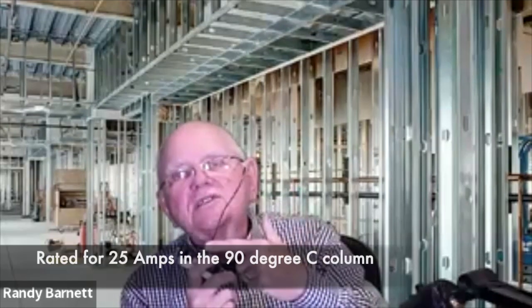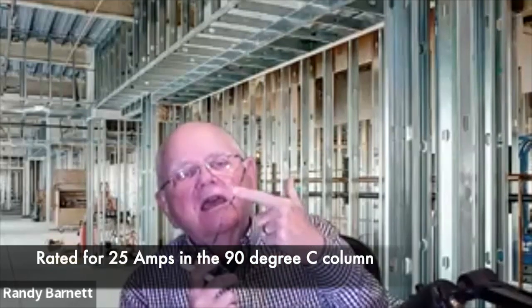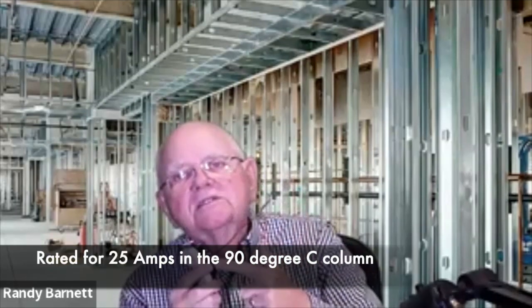Well, should it? No. I've got a wire that's rated for 25 amps, and it's limited because of the device, which is inside of a box, by the way, right? I'm limited to 15 amps of current flow on that. I always thought of that, well, that's kind of a lot of overkill, isn't it? That's a good thing. Sounds like it to me. Be safer. So anyway, that's my temperature limitations.